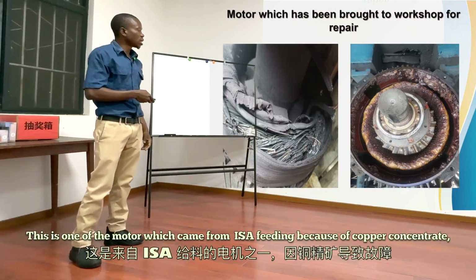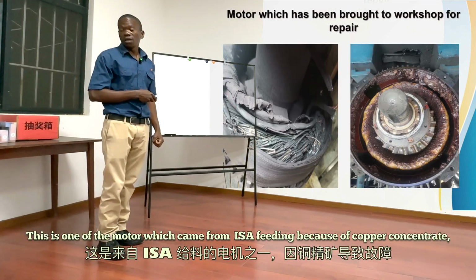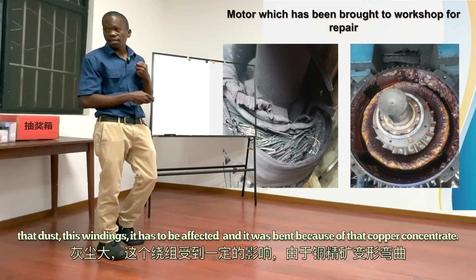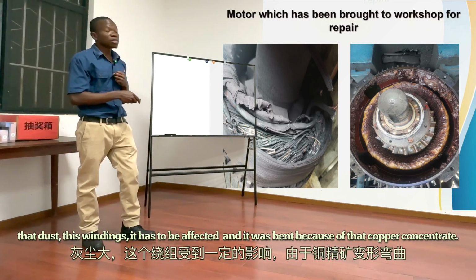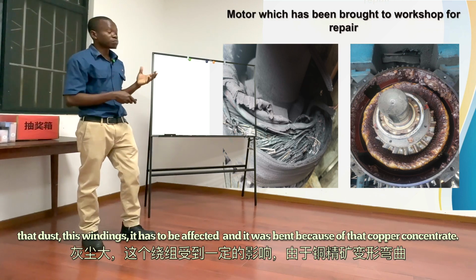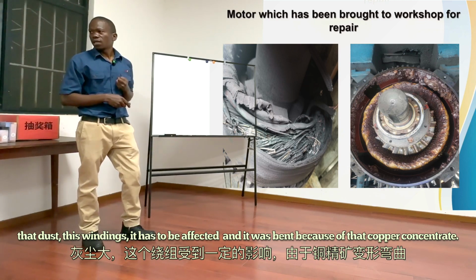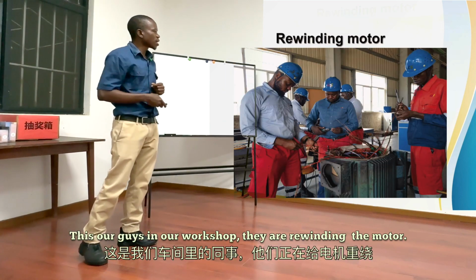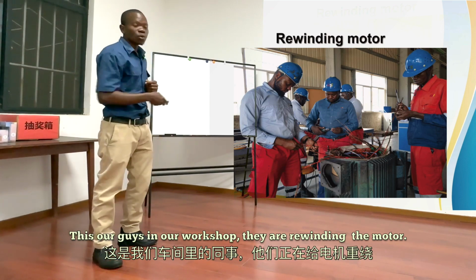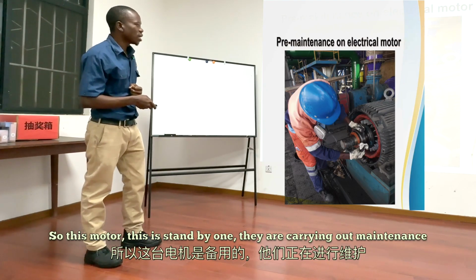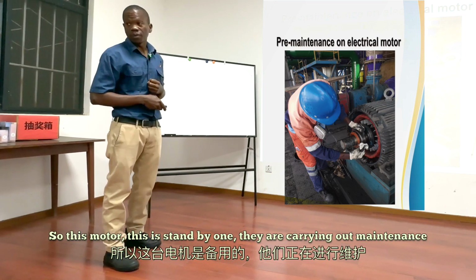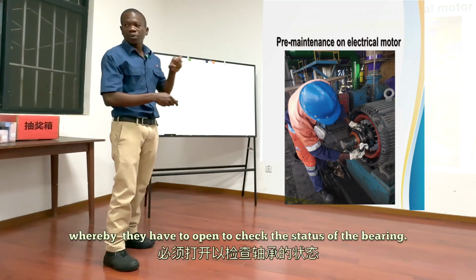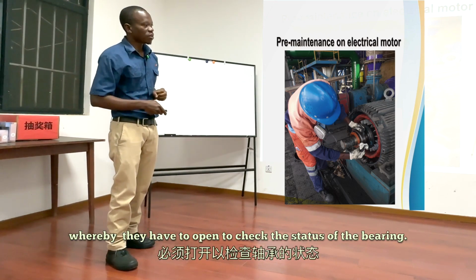This is one of the motors which came from ISA feeding. Because of the copper concentrate dust, the windings were affected and bent. These are our guys in the workshop, they are rewinding the motor. This motor is a standby one. They are carrying out maintenance, whereby they have to open it to check the status of the bearing.